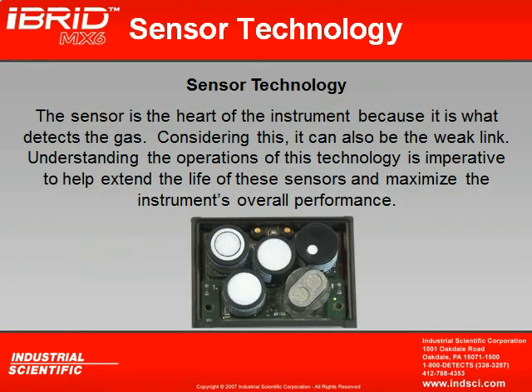Before we can really get into the maintenance of the instrument, we do need to discuss the sensor technology. The reason we have to talk about sensor technology is because this is truly the heart of the instrument. It is what actually detects the gas. Considering this, though, it can also be the weak link. Nine times out of 10, when something goes wrong with the instrument, generally it's sensor related, and all you have to do is change out the sensor to make it all better again. Understanding the operations of this technology is imperative to help extend the life of these sensors and maximize the instrument's overall performance.